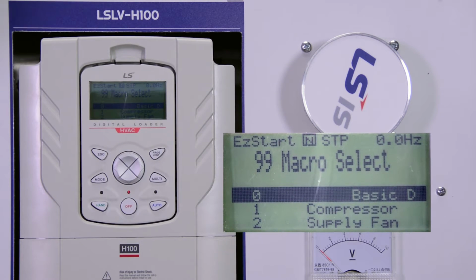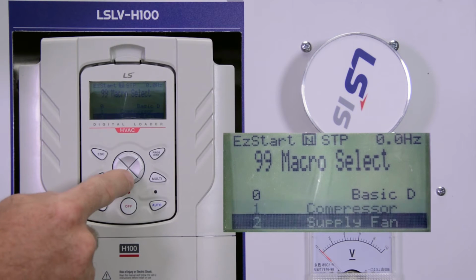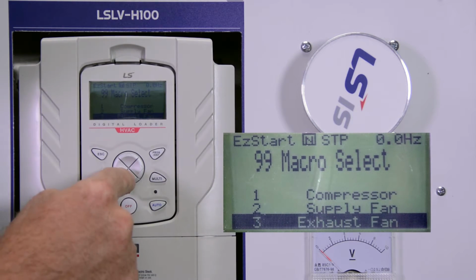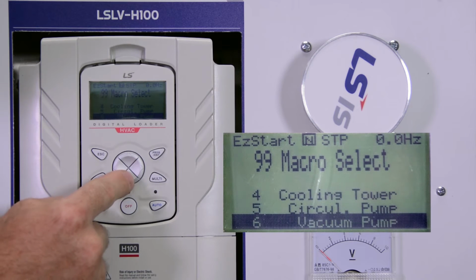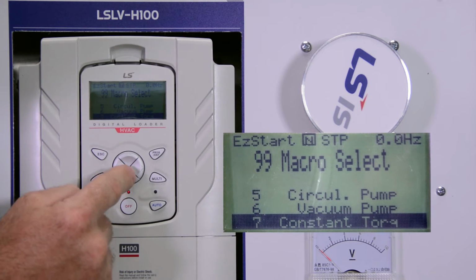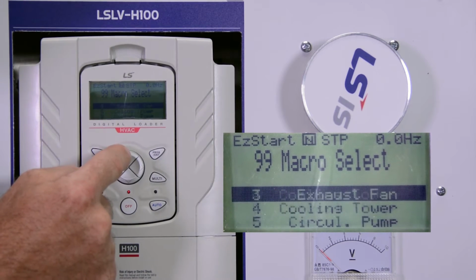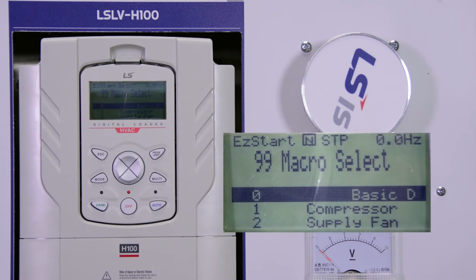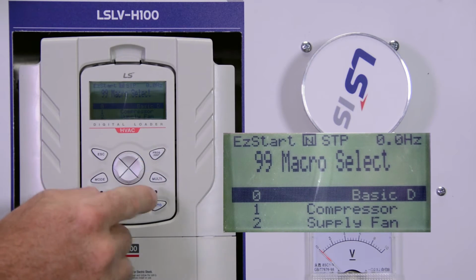The first question is, do you want to use a macro? If you select basic, that's no macro. We do have some macros that you can use for specific applications: compressor, supply fan, exhaust fan, cooling tower, circulation pump, and vacuum pump. If you do select a macro, it's going to automatically assume that you're going to need a PID feedback signal. So if you're not using the internal PID control for the H100 drive, then don't select a macro. So we're going to do basic for this one.